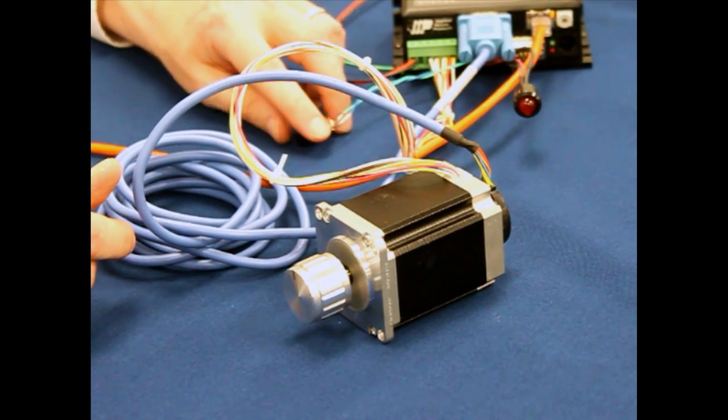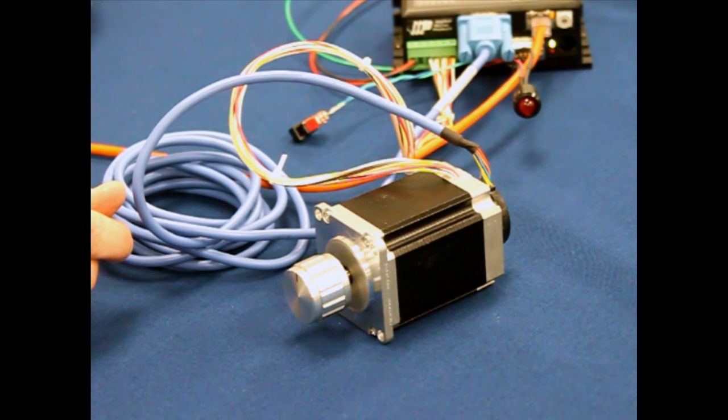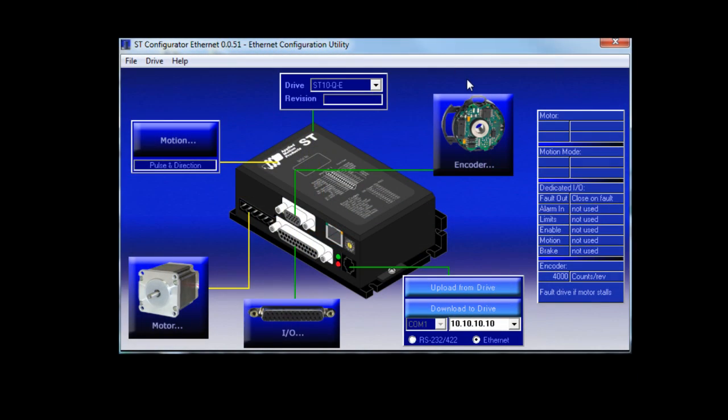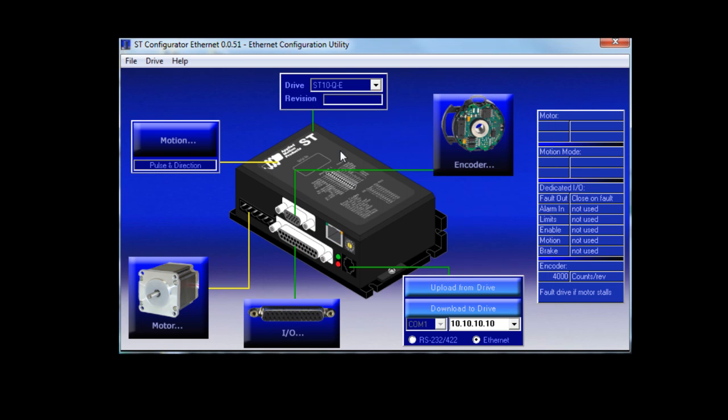Now this is what you get with an open loop system. Now we're going to use the ST configurator software to turn on stall detection. First I'll open the encoder dialog and select fault drive if motor stalls. I've already set the rest of the encoder settings, so I'll click OK to dismiss that dialog.